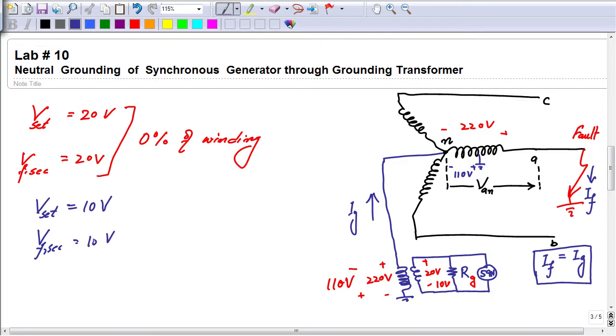So it means the relay is not going to operate, because the fault voltage available across this grounding resistance and the set voltage are both equal. So if a fault occurs at this midpoint here, the relay is not going to operate for this fault. If the fault moves from the midpoint towards the main terminal of the winding, the voltage will exceed 110 and this Vf secondary would increase above the 10 volt, and the fault will be detected by the relay.